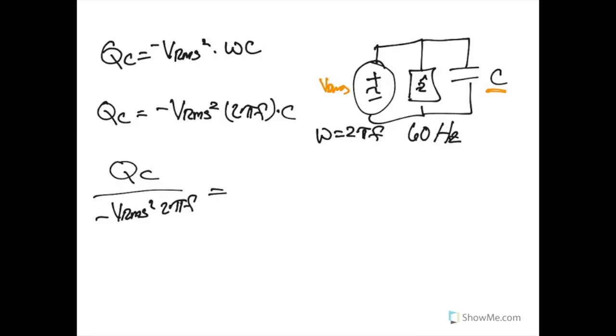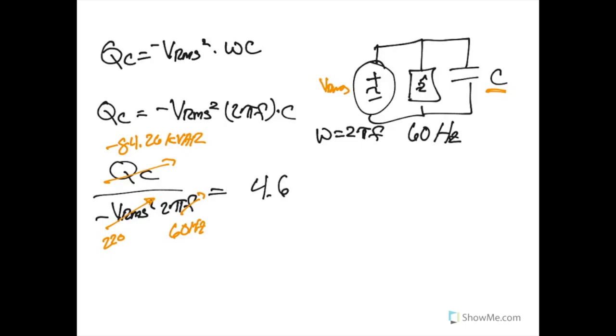Plugging in all final values: Qc was negative 84.26 kilovars, the voltage source is 220 volts RMS, and frequency is 60 hertz. After these calculations, we find we need a capacitor of 4.62 millifarads.